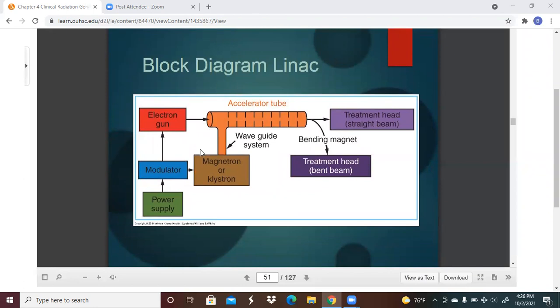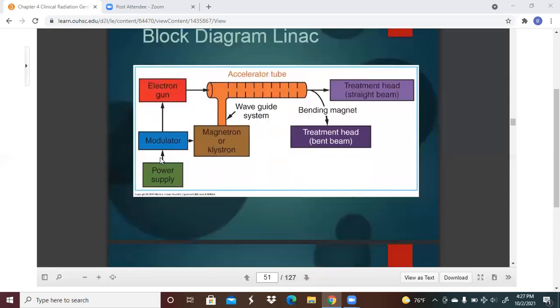Okay, so if you were to take all of these components that were just mentioned and just draw pictures as opposed to looking at what an actual setup might be, you've got the power supply, so you've got the power coming in, you've got the modulator, you've got the magnetron or the Klystron, the waveguide system, and the electron gun fires it down, you've got the accelerator tube, you've got a bending magnet, which then leads into the treatment head, or it goes straight into the treatment head with a straight beam. Kind of depends on the design.